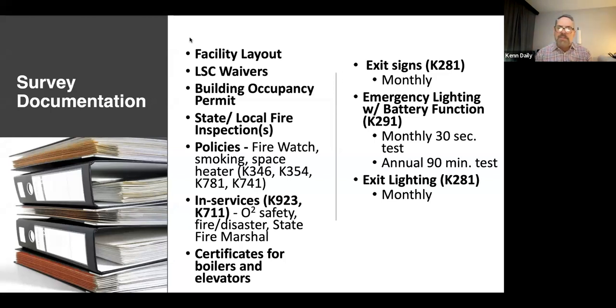So you have that documentation for all of your battery operated devices. Most of you may have these on the generator, so that's separate. We'll talk about K-tag 281 in a second. But at 291, you would have any battery operated device, and we have at least one of them, the transfer switch. So if your transfer switch or generator are inside your building, one or both, you're supposed to have no less than one of these battery operated emergency lighting devices at the transfer switch inside the room.